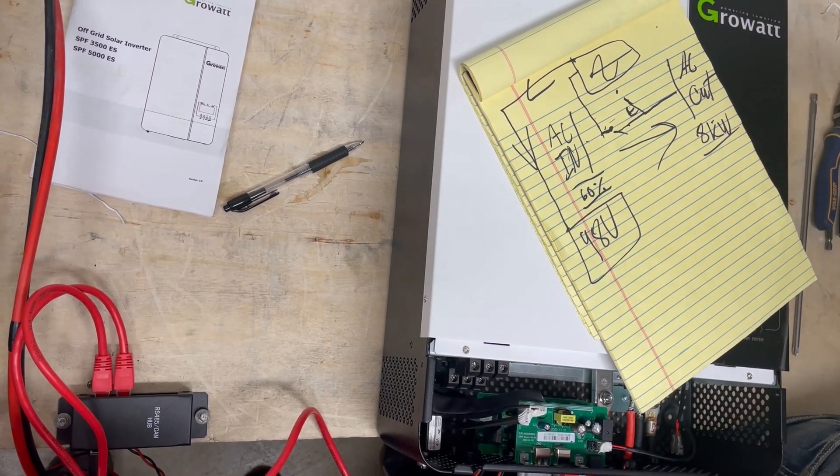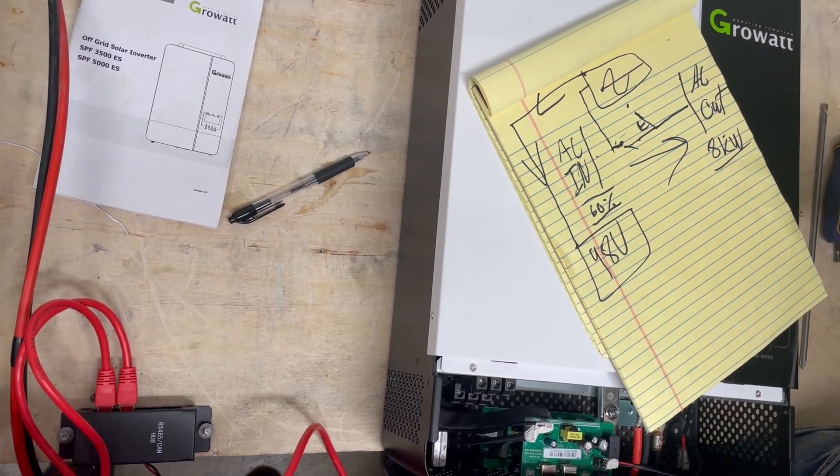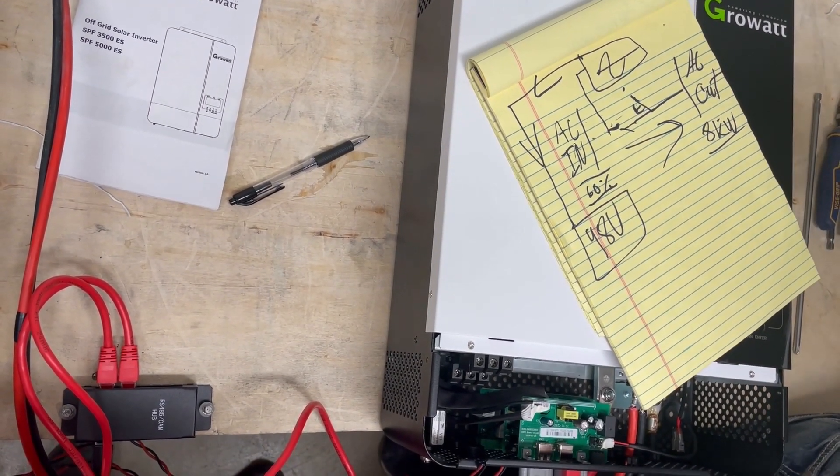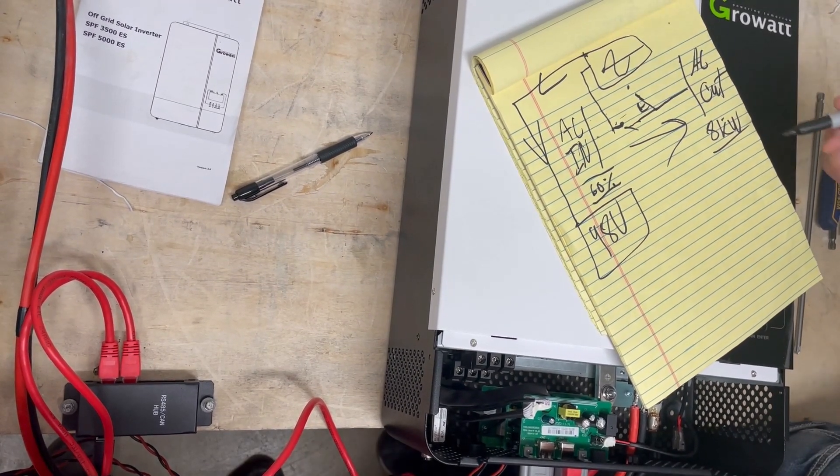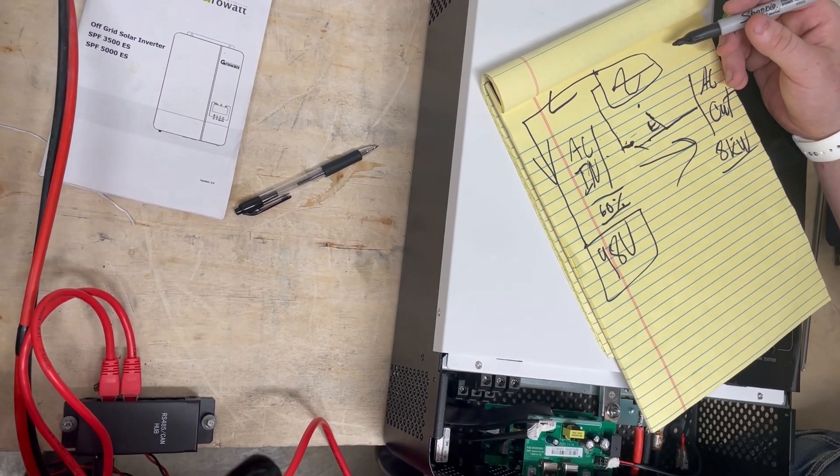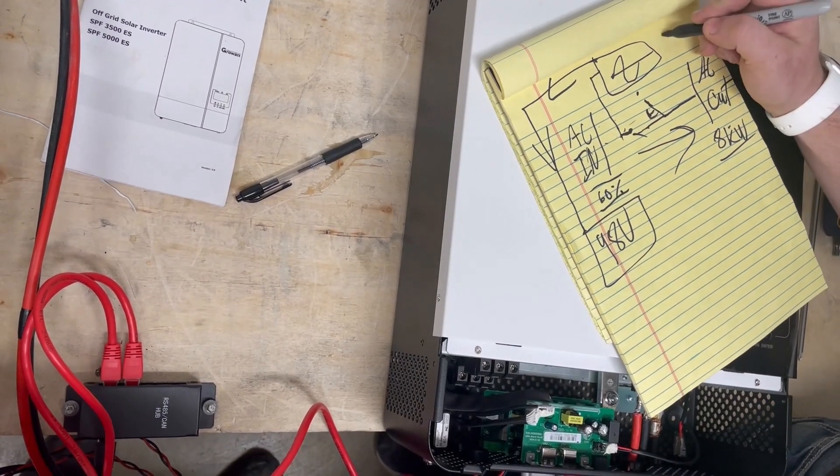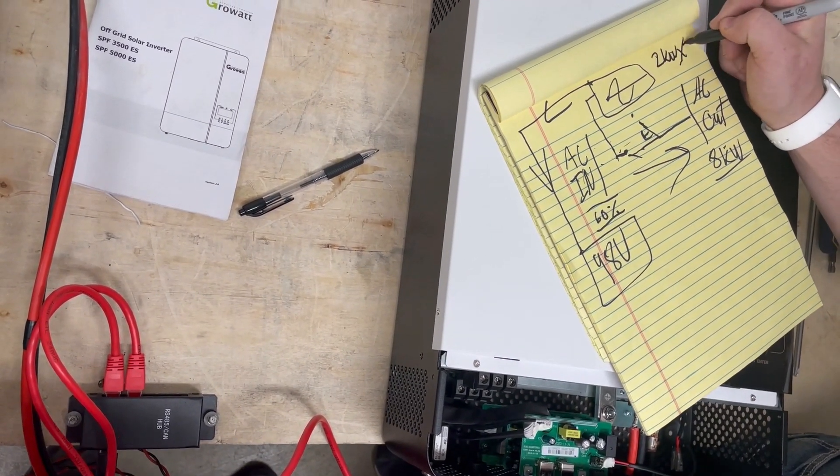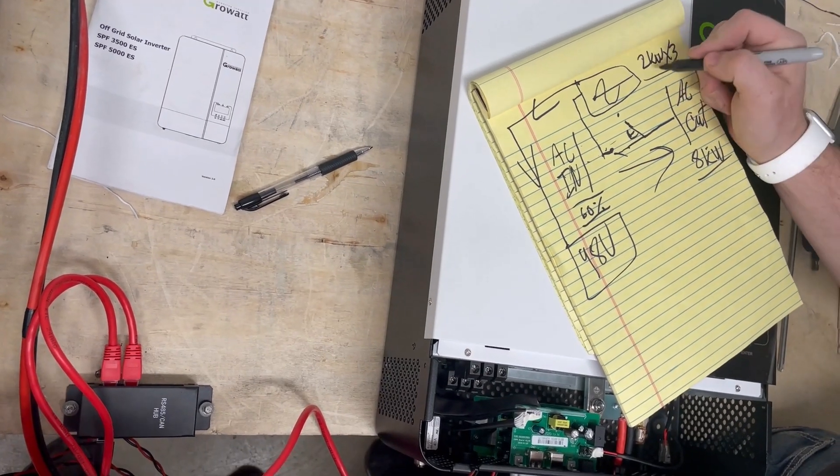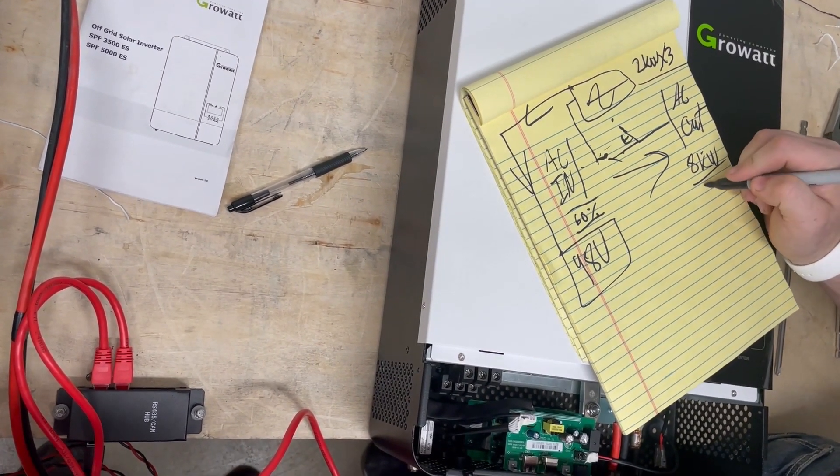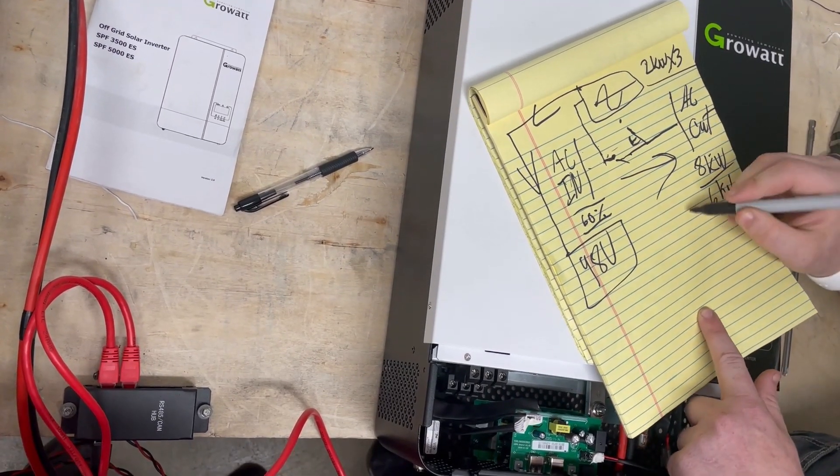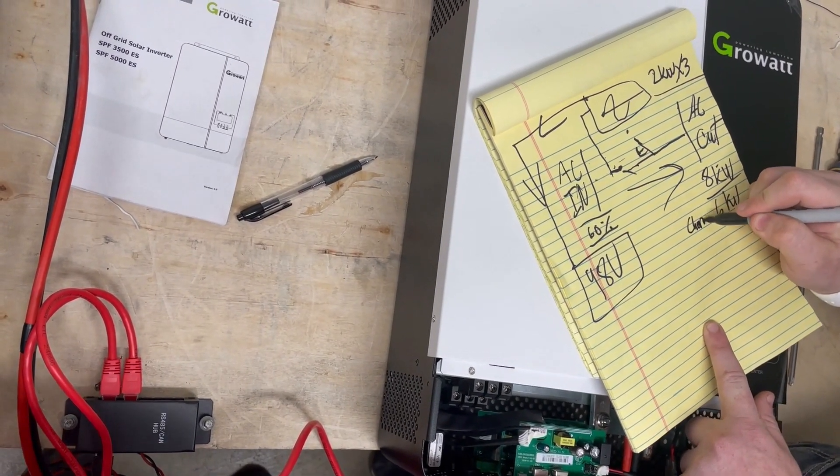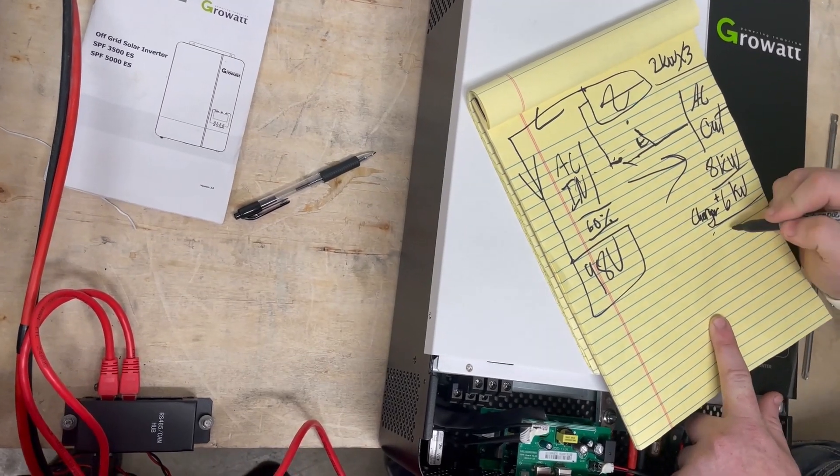It will cause damage to the electronics which are hooked directly to the generator. So if you want to use an inverter in charger mode, you have to have massive superiority in sizing. So what's the right size generator for this? Let's say I cut my inverters down to half, to 2 kilowatts each. 2 kW times 3, that's 6.